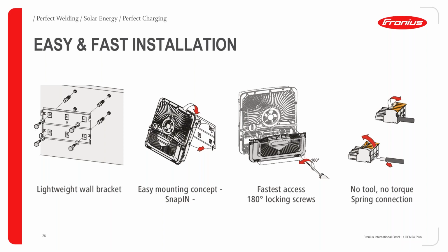When we open it and look into the connection compartment, we see the next new item: the spring lever connection. So there's no screwing needed for connecting the cable to the inverter either - we just put the cable in and close the lever, the spring connection. There's no torque issue anymore, no tool needed. Then we plug the whole connection terminal into the device itself and we're finished. It's really a rapid, fast installation, and also rapid service is possible with this device.